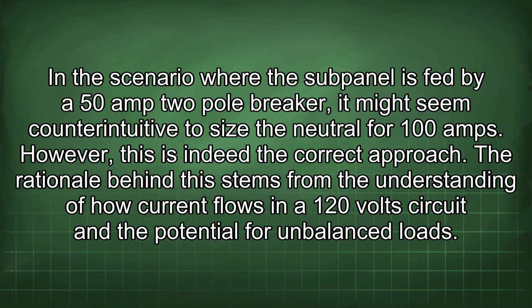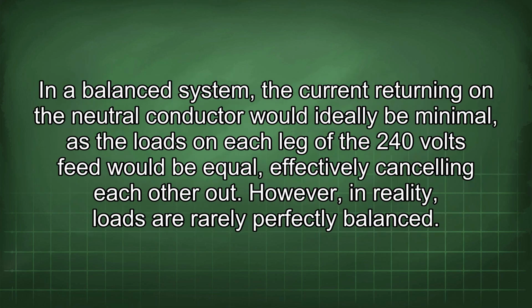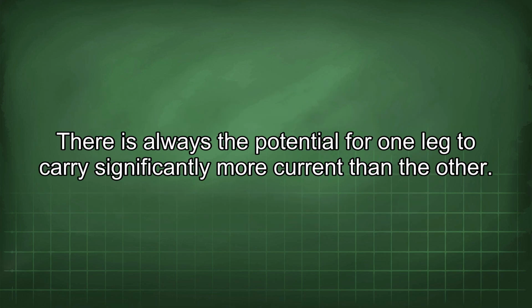The rationale behind this stems from the understanding of how current flows in a 120-volt circuit and the potential for unbalanced loads. In a balanced system, the current returning on the neutral conductor would ideally be minimal, as the loads on each leg of the 240 volts feed would be equal, effectively cancelling each other out. However, in reality, loads are rarely perfectly balanced. There is always the potential for one leg to carry significantly more current than the other.